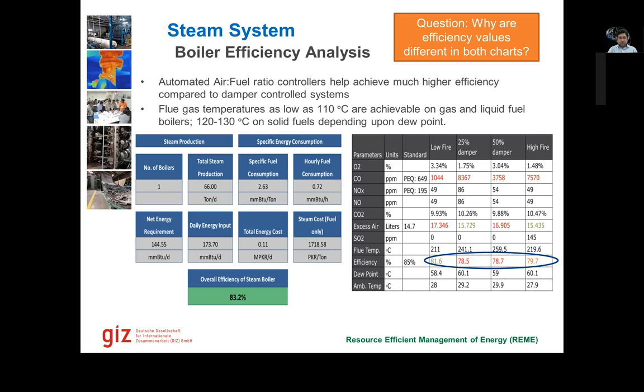based on the flue gas temperatures, oxygen content, and moisture content, as well as ambient temperature. So it does stoichiometric efficiency calculations inside the tool. So these are two different methods. A stack analyzer only provides you the efficiency of the combustion process, not the whole boiler. So that is why there's a difference. So I recommend that you usually calculate both efficiencies, so that we have a real value.